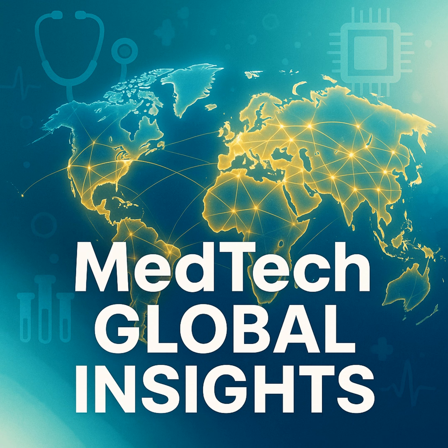Consider a successful American company with an FDA-approved knee replacement system. They decide to expand into the European Union and Australia. They quickly discover their existing technical dossier is insufficient for the EU MDR. Their clinical data needs to be supplemented, and their risk management files must be updated to meet the new, stricter requirements. Simultaneously, for Australia, they need to appoint a local TGA sponsor and adapt their submission to local standards, even if they can leverage their US approval. This dual-front effort becomes a resource drain, delaying market entry by months, if not years.